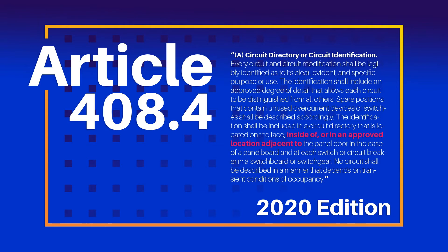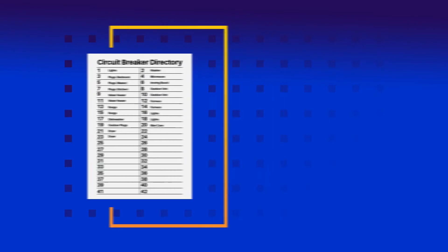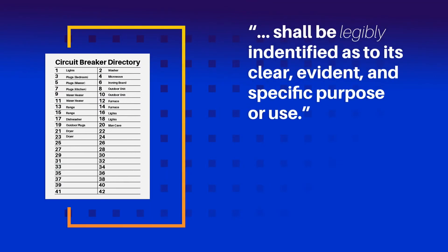With this added language, the code now allows for more written detail. Instead of having a circuit directory say 'lights,' you can now clarify each entry on the schedule and not have to fit it on the factory-provided materials. Either way, the code maintains that every circuit and circuit modification must be legibly identified as to its clear and specific purpose.